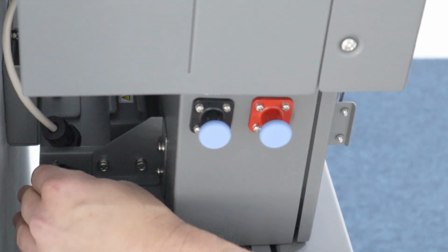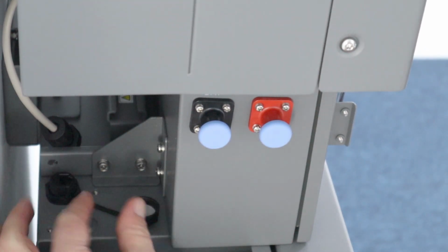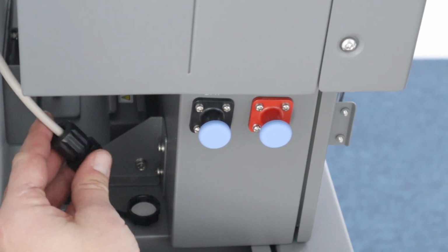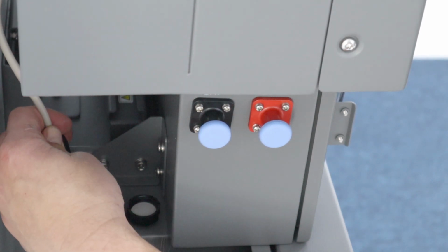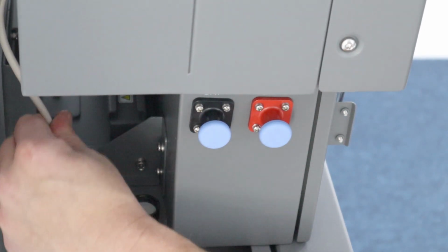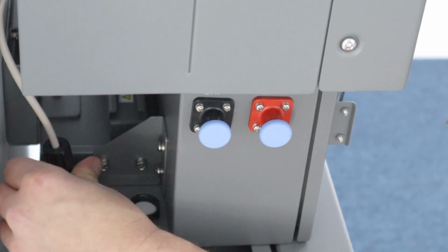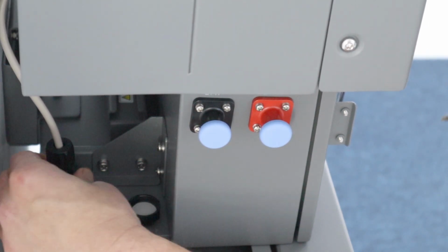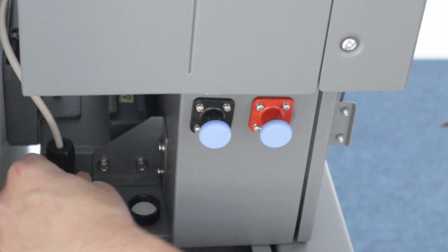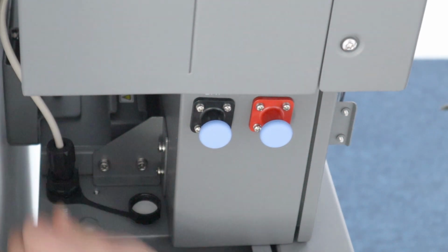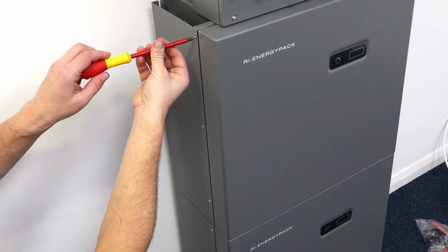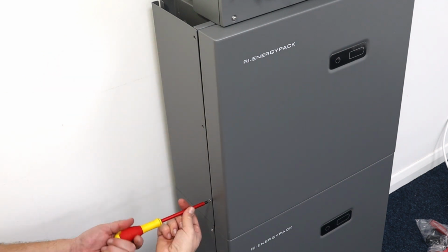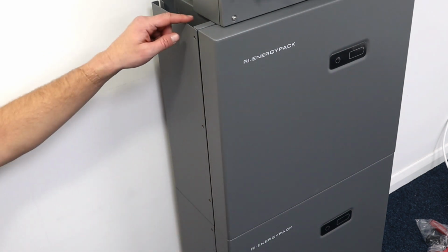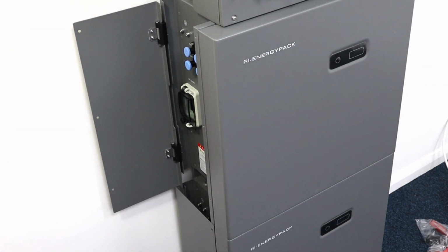Next, unscrew the communications port cap on the top battery and connect the other end of the communications cable that you connected to the back of the inverter earlier, making sure it is screwed down securely. This enables communication between the battery and inverter. Remove the 3 retaining screws on each of the battery access panels and open them to reveal the battery connection ports.